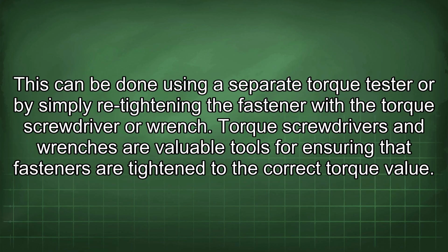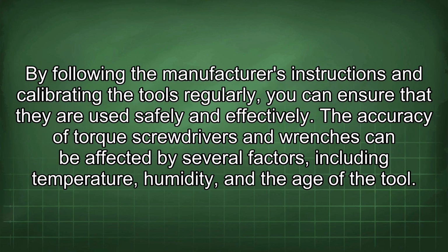This can be done using a separate torque tester or by simply retightening the fastener with the torque screwdriver or wrench. Torque screwdrivers and wrenches are valuable tools for ensuring that fasteners are tightened to the correct torque value. By following the manufacturer's instructions and calibrating the tools regularly, you can ensure that they are used safely and effectively.